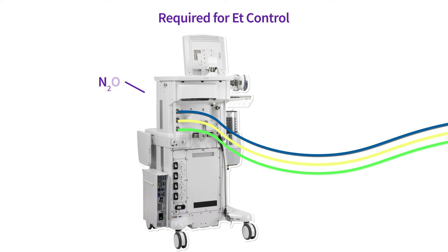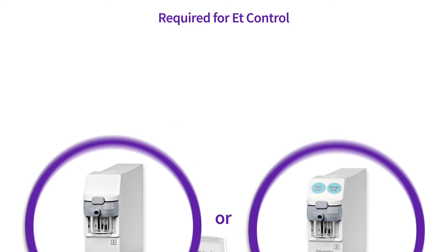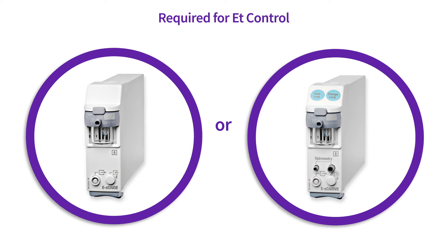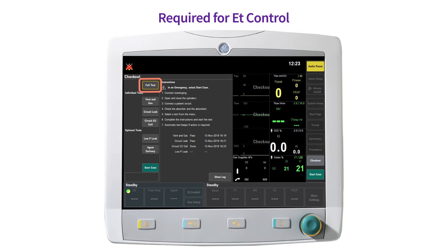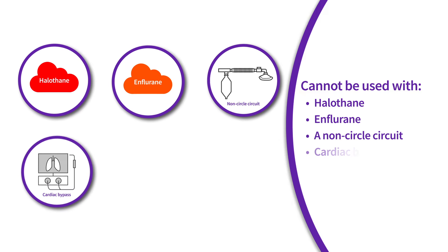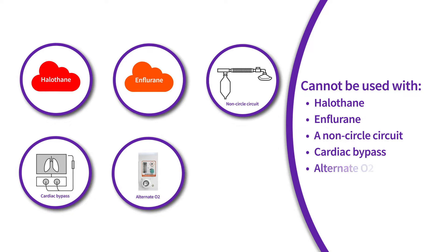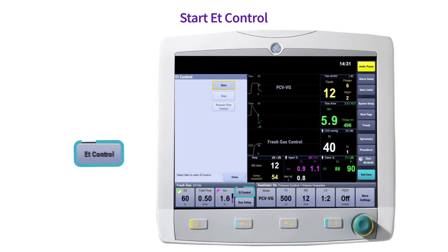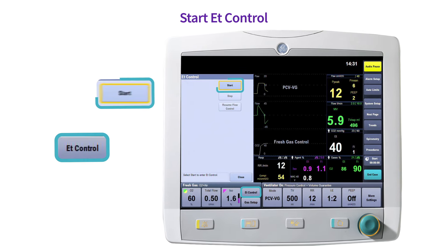The Aisys CS2 anesthesia delivery system should have a supply of oxygen and balance gas to enter end-tidal control mode. A CARESCAPE airway module with end-tidal control capabilities should be installed and warmed up. A full test checkout should be completed prior to use. It is important to note that end-tidal control cannot be used with halothane, enflurane, a non-circle circuit, cardiac bypass, alternate O2, and air-only modes. To enter end-tidal control, select ET control from the fresh gas panel and select start.